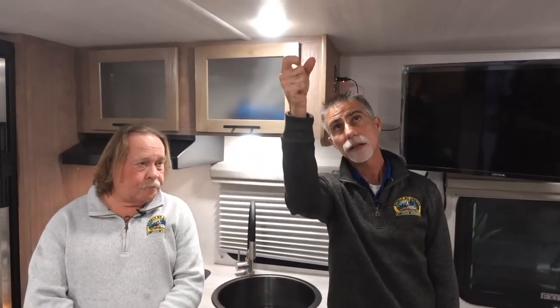I'm trying to just help you avoid coming in for a service call on something that there's nothing wrong with, because it happens all the time. People are like, oh, it's not working right. They're going to come out, and the guy's going to take a little laser heat gun and hit the air going in, hit the air going out, and it's 24 degrees colder, and we're good. There's no warranty. It's just the way the thing works.